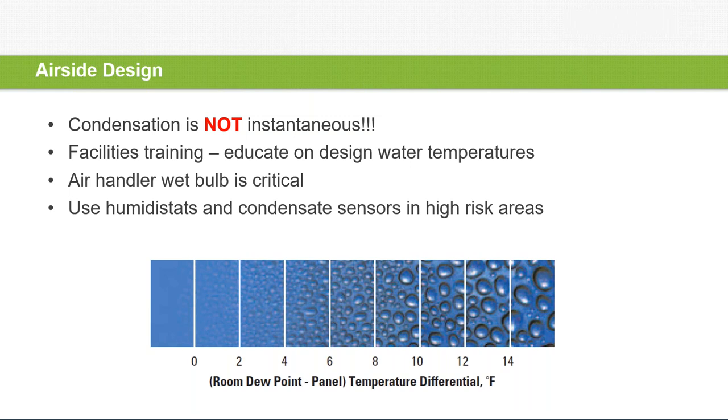That's the second scenario I've seen condense. So neither issue is really a chilled beam issue, but it is a system level issue. So if you're monitoring these spaces and you see a scenario coming in where the entering water temperature is below the space dew point, just take a look and then start to figure out what's going on, why that's happening, and ways to mitigate that.